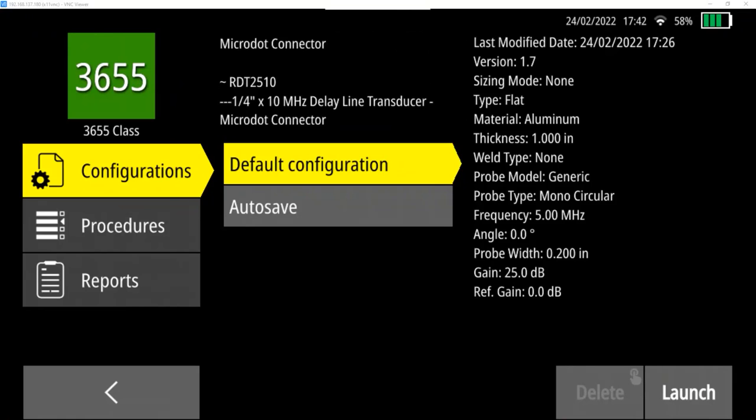And then finally, the last straight beam transducer that's available is the RDT2510. And this is a one-quarter-inch, 10 megahertz delay line transducer. So in this case, the transceiver is offset from the workpiece in order to look at thin materials or materials where there may be flaws near the surface.